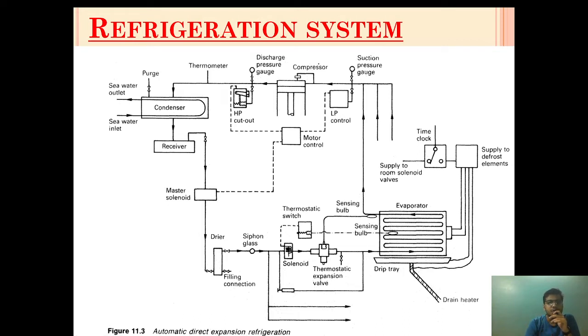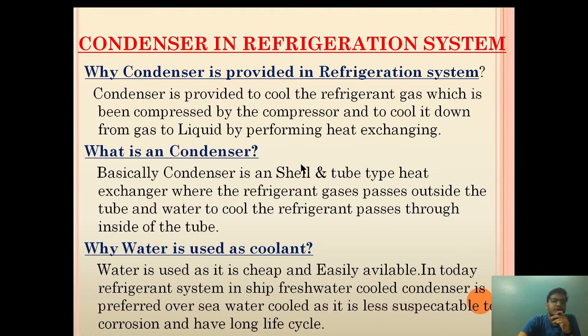Basically, the purpose of condenser is to extract the heat which has been absorbed during the work done of compression and to cool it down and change it into liquid refrigerant. So what is a condenser? Basically, the condenser is a shell and tube type heat exchanger where refrigerant gas passes outside the tube and water to cool the refrigerant passes through inside the tube.